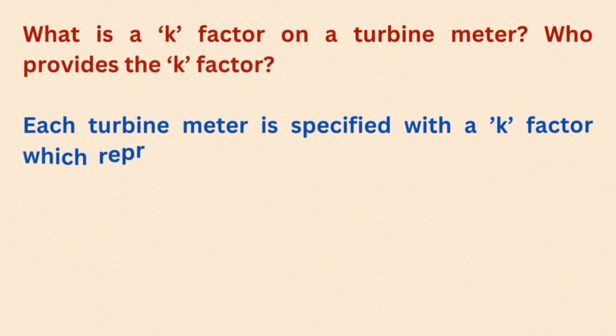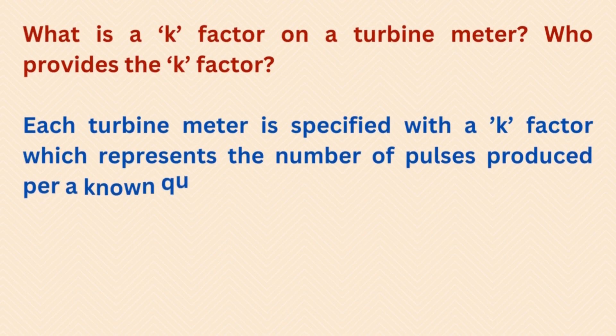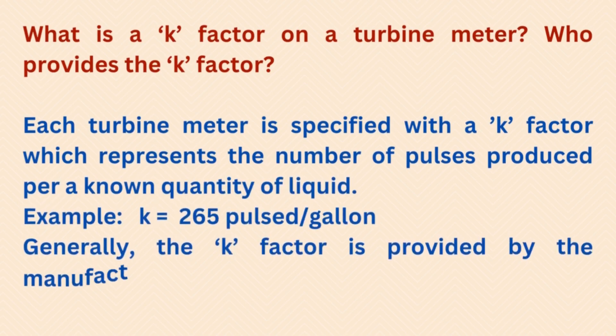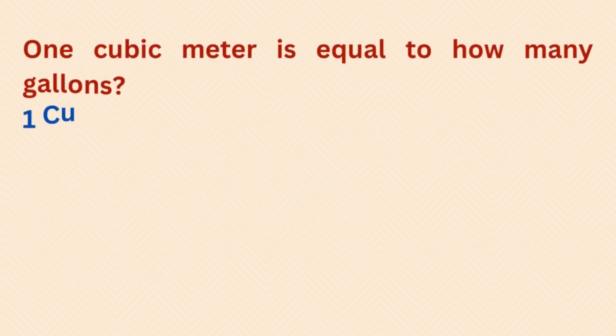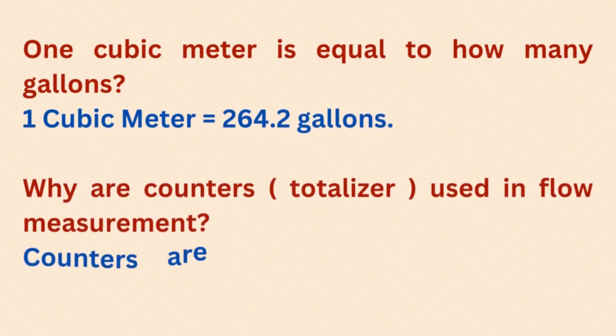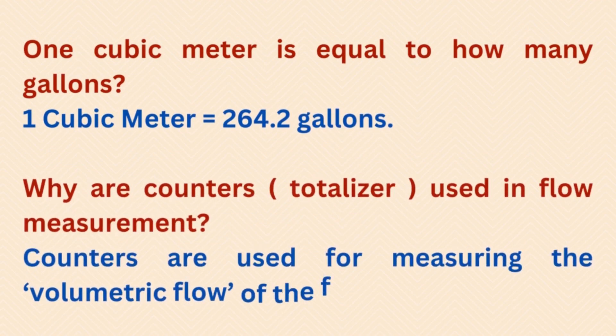What is a K factor on a turbine meter and who provides it? Each turbine meter is specified with a K factor which represents the number of pulses produced per unit quantity of liquid. For example, K = 265 pulses/gallon. Generally the K factor is provided by the manufacturer. One cubic meter is equal to 264.2 gallons.